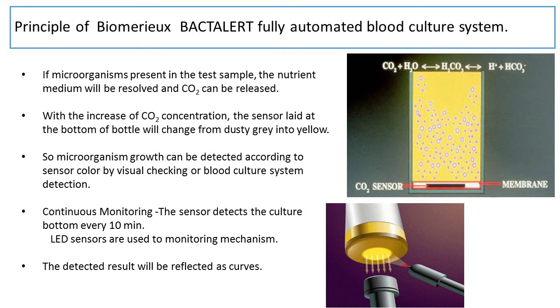The blood culture system performs continuous monitoring, detecting the culture bottle sensor every 10 minutes. LED sensors are used in the monitoring mechanism, and the detected results are reflected as curves.